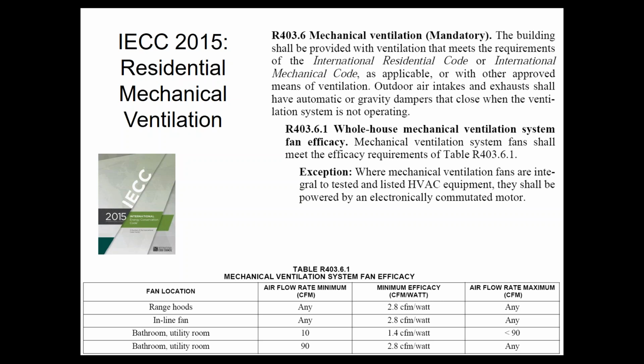And you look at that below and you're like, range hoods, bathroom fans, who's using that for ventilation? That's kind of weird, right? You're probably using your furnace or an ERV. Well, if you're using your furnace or ERV for your ventilation system, then that table doesn't apply to you. Instead, you have to have an ECM motor. If your equipment is tested and listed equipment, and that's being used for ventilation, it has to have an ECM motor. ERV is tested and listed per HRI. So that would have to have an ECM in it. You cannot put in a regular ERV with a PSC blower.